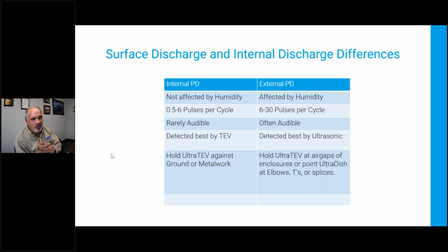In order to do a TEV test, you're going to hold the equipment tight up against the ground or against the metalwork of the switchgear, because I want to measure that voltage, as opposed to an ultrasonic test where I'm going to be looking for sound waves traveling through the air. So I'm going to hold it away and move it around to the louvers and air gaps.